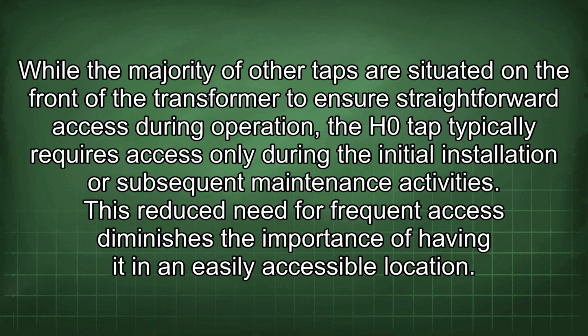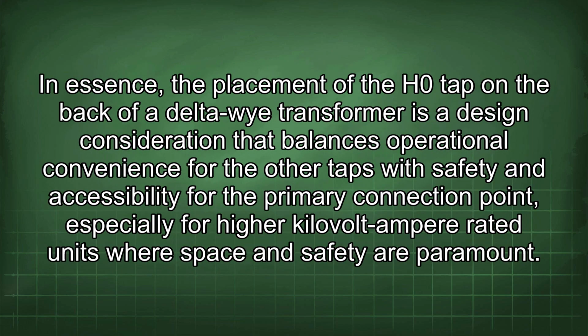This reduced need for frequent access diminishes the importance of having it in an easily accessible location. In essence, the placement of the H0 tap on the back of a delta-wye transformer is a design consideration that balances operational convenience for the other taps with safety and accessibility for the primary connection point, especially for higher kilovolt-ampere rated units where space and safety are paramount.